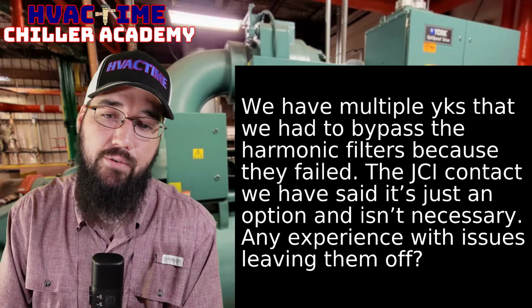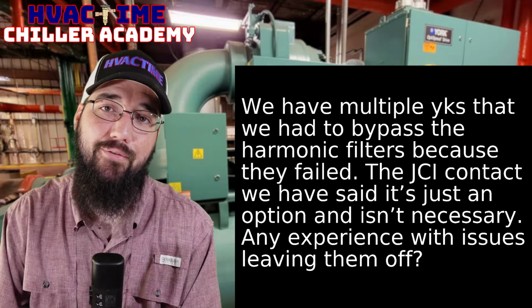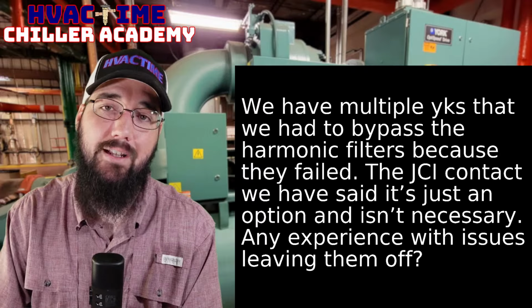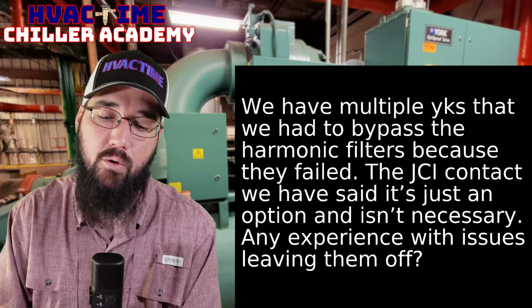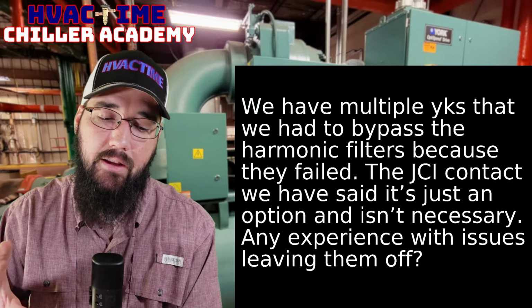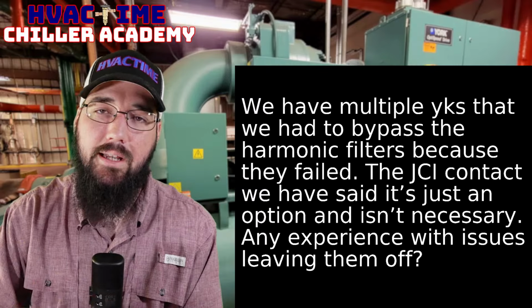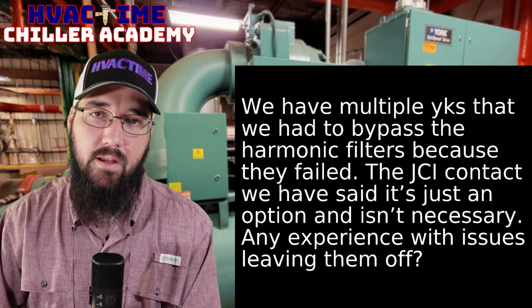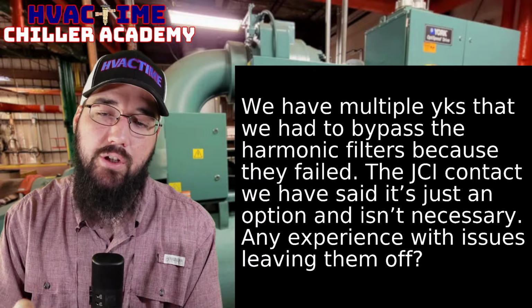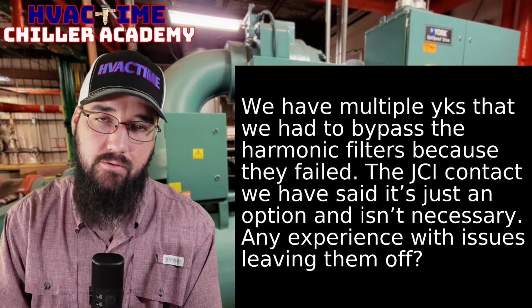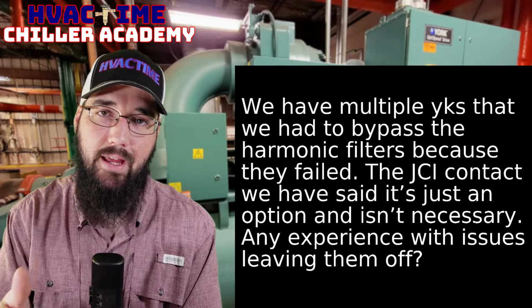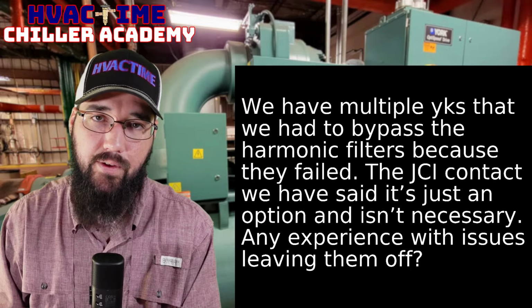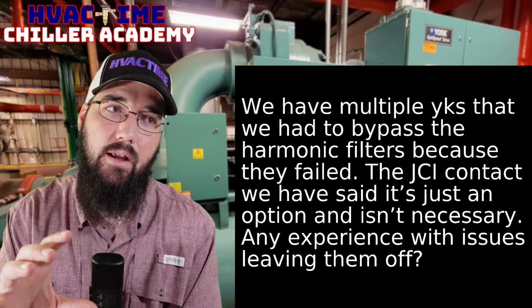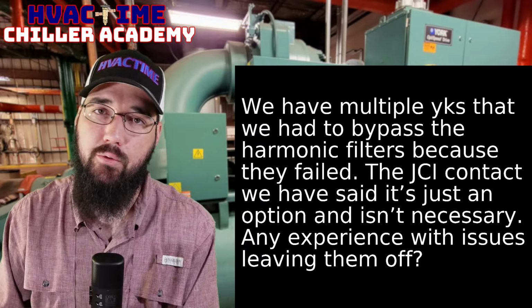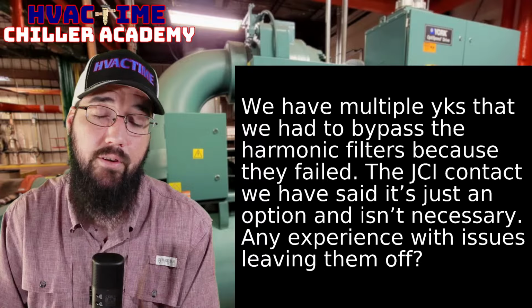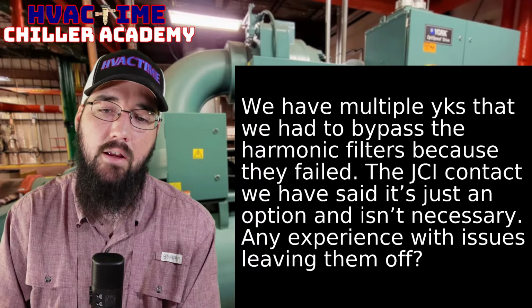And then the harmonic filter is taking that a step further and further filtering those to try to clean them up more and purify them more so that we have a cleaner feed in. So for the machines where it is an option, yes, you can remove it if it fails, and it will function just like the other machines that didn't ship with it from the factory. It's fine.